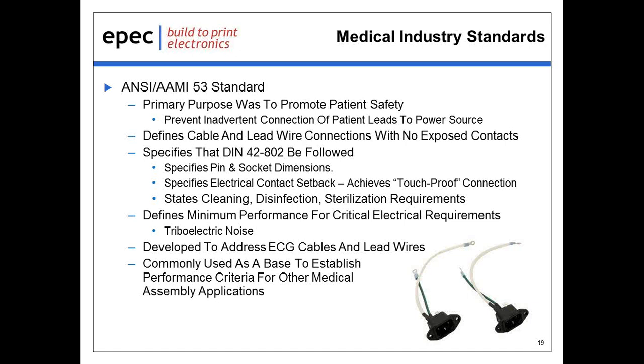The ANSI 53 standard also details the correct methods to clean the assemblies and the machines they're connected to, the correct way to disinfect the components, the various ways to sterilize the products, and for how long they should be exposed to the sterilization process. Also included in the spec are the minimum performance criteria for some of the electrical characteristics to prevent or diminish any triboelectric noise. It also specifies the test methods that we need to utilize to find out how much triboelectric noise our assembly is really creating.